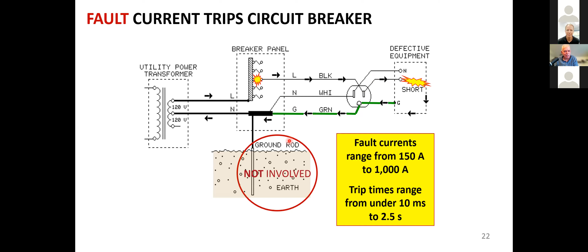But fuses and circuit breakers are generally slow in order to tolerate startup for motors like refrigerators and air conditioners, but that also makes them slow to respond to faults. But it's enough to protect the wiring, and that's the intent. The wire doesn't get hot enough to start a fire.